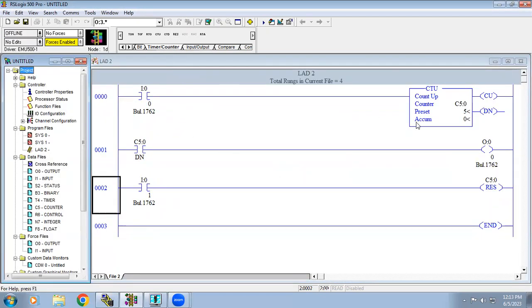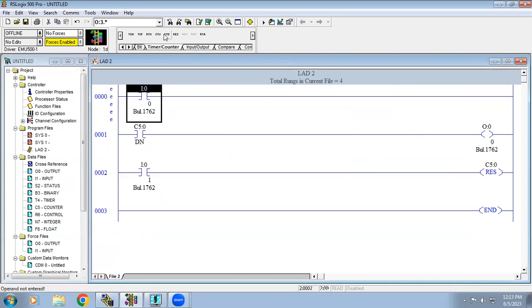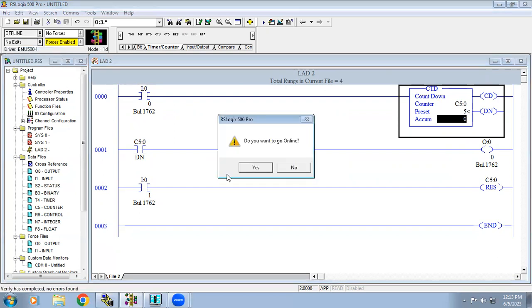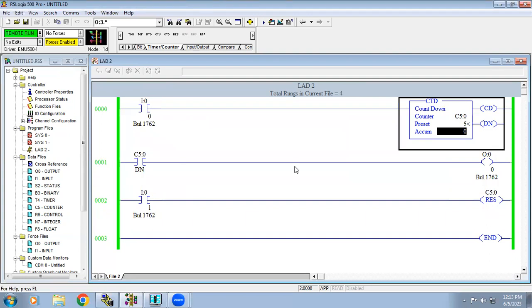Now we have the down counter. I'll delete this block and add the down counter using the same address. In a down counter, the accumulator value starts at the preset value instead of 0. So whatever preset value is given, it starts from there.